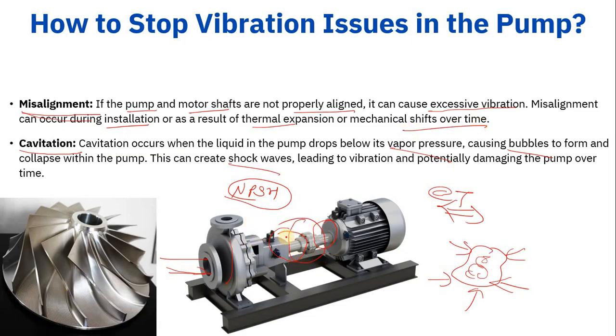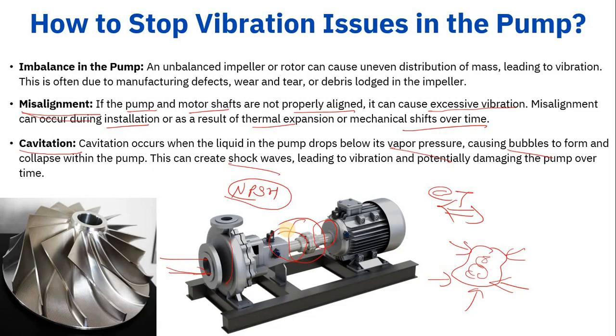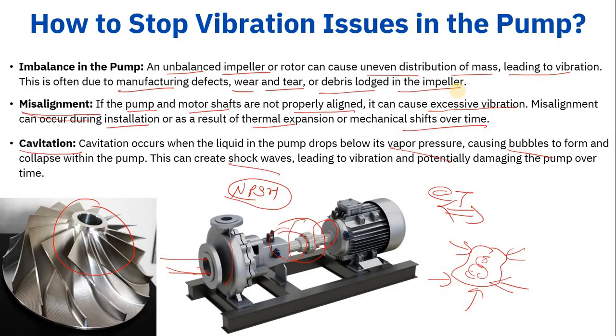We must ensure that whenever the operator takes a round, it is their responsibility to check shaft alignment. Regarding imbalance: an imbalanced impeller or rotor causes uneven distribution of mass, leading to vibration and potential casing damage. This is most often a defect from the manufacturing side, or it can result from wear and tear if solids or debris enter the impeller.